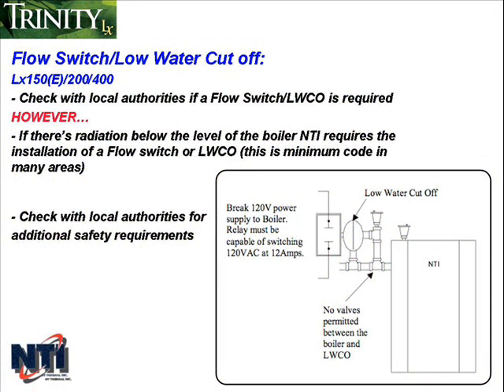When external safety devices are being used, such as a low water cutoff, flow switch, or a temperature limiting switch, they can be wired directly into the low voltage terminal strip. We'll cover that in the wiring section of the training. The Trinity Lx 800 comes equipped with a factory installed flow switch installed in a 2-inch diameter line. The flow switch is pre-plumbed with a NEMA 4 rated enclosure and pre-wired via liquid tight conduit. According to ASME CSD1, a flow switch must be used in lieu of a low water cutoff for a water tube boiler.